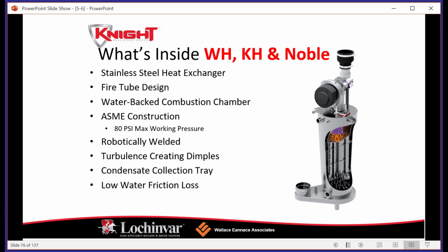On our fire tube boilers, which again is the Crests, it's the Knights, the non-Knight XL product line, you're gonna have a fire tube design. And what this means is now you can see on the right-hand side, there's a little cutaway. The energy is coming through the top of the heat exchanger. We're creating that flame, we're creating that heat using that metallic fiber mesh, and we're pushing it down through a series of tubes where the water is surrounding it. So that's what we say we're doing the water back combustion chamber. And again, there's turbulence creating dimples.